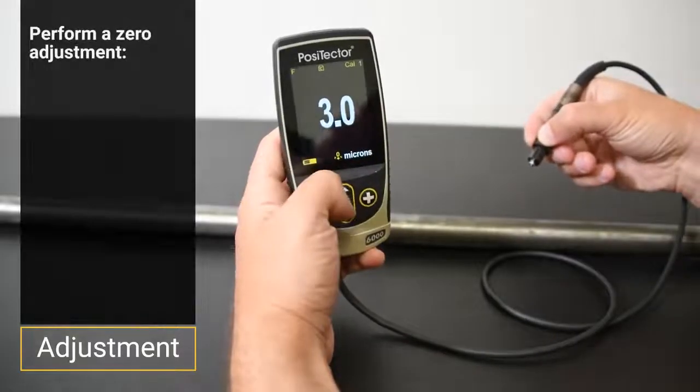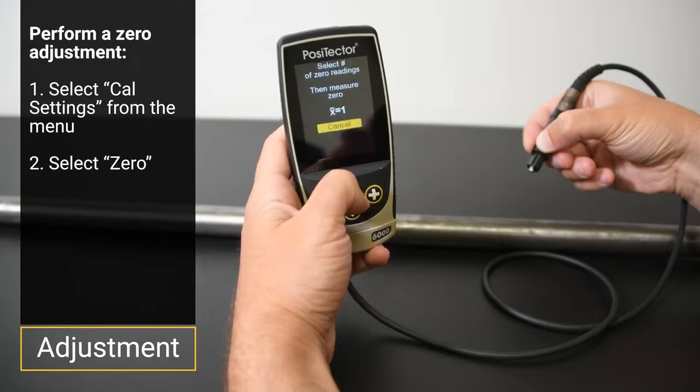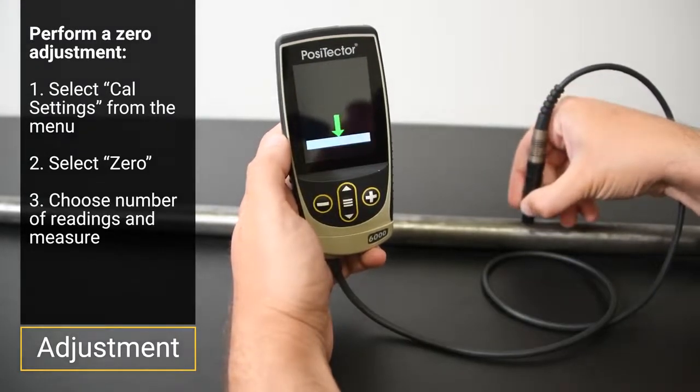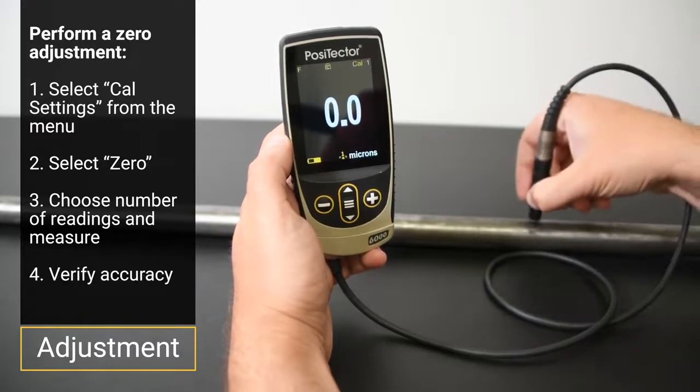To perform a zero adjustment with the PosiTector 6000, select Cal settings from the menu, then zero. Take one or more measurements by following the on-screen prompt. When completed, verify that the instrument measures within tolerance of zero.